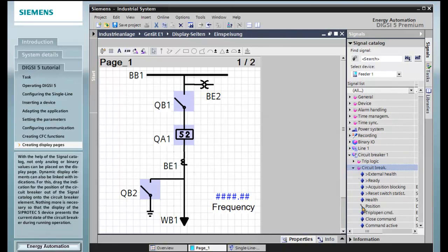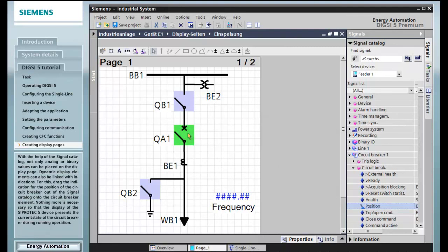For this, drag the indication for the position of the circuit breaker out of the signal catalog onto the circuit breaker element. Nothing more is necessary so that the display of the Siprotec 5 device presents the current state of the circuit breaker during running operation.